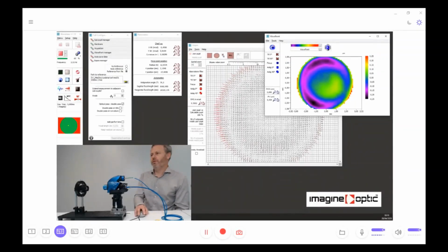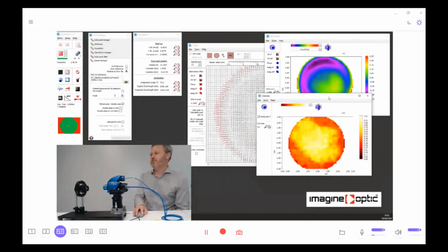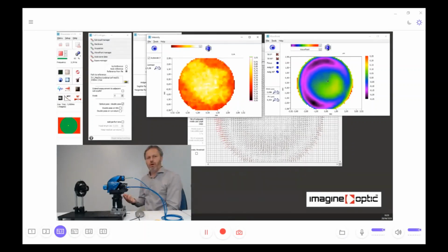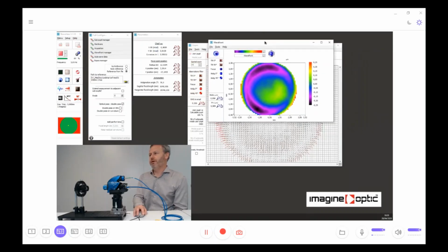It is also possible to retrieve the intensity of the beam. And here you have live intensity and phase, so amplitude and phase. In one single image, we're able to measure the electrical field of light. This feature is very interesting for laser applications, for instance, to measure intensity and phase and to know how the laser will focus by just propagating using a Fresnel propagator, for instance. But here we are doing metrology, so the important information we'll use here is the wavefront.